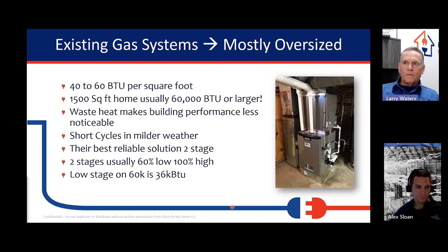We know with a house that's 1,500 square feet, we usually have a furnace in there that's at least 60,000 BTUs. There's a ton of waste heat on these systems. Because they're way larger than they need to be, people don't notice that they don't work well. These systems always short cycle in mild weather, so the furnace just runs a little bit of time. A good rule of thumb that I use all the time: if you have a customer that says my house heats really well, it warms up in 10 minutes, or it gets hot in 10 minutes, that's not a properly sized system. So the best reliable solution for unitary is really two stage, which is also not that reliable. Two stages are usually 60% low or 100% high, and the low stage on a 60,000 BTU is just 36,000 BTUs. So that's going to match what your heat pump would be all the time.